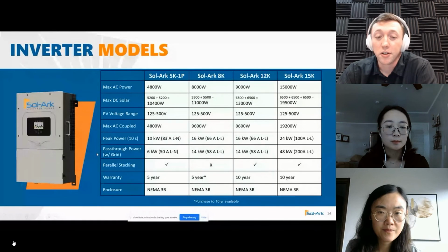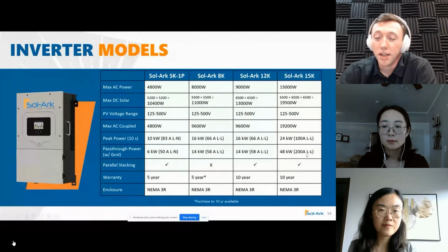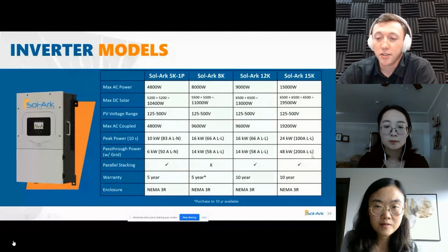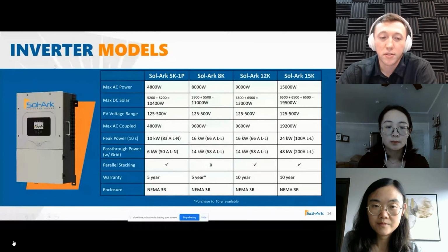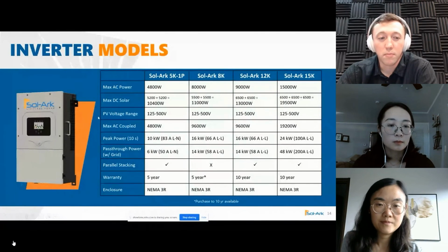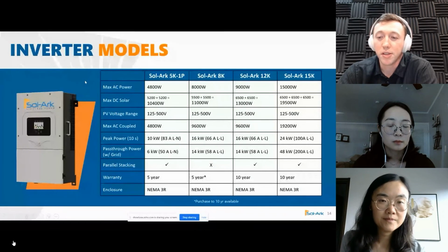Another fact here is our pass-through with the Sol-Ark 15K. We love to talk about this aspect of the inverter. It actually has a 200 amp pass-through, and that's why we call it the whole home backup. You can directly tie in your grid connection into a disconnect, and then from that disconnect directly to the grid connection of a Sol-Ark inverter, and provide 200 amps of service from that utility all the way to the load output of the Sol-Ark inverter. That means you have no transfer switch needed. There's no critical loads or sub panel. You can just keep your normal 200 amp service that you have at most residential homes across the United States. It'll be able to provide that power.